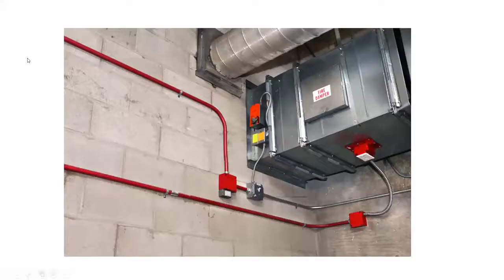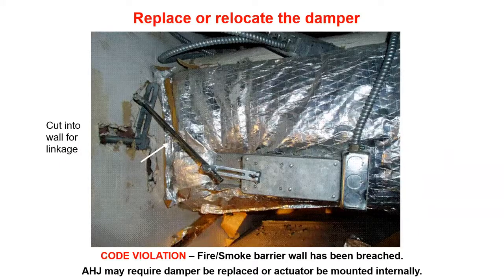Next. Now, when you go to look at some of them, and this one's typical, you can't tell really whether that is a Chapter 9 or a Chapter 7 application. The red conduits give you a definite indication that it was installed by a fire alarm contractor, but we see a mistake up at the top. Oh, fire damper. Well, it's not a fire damper. It's got an actuator on it. It's going to be a smoke damper, or because I can see a high temperature limit, it's a combination fire and smoke damper. So you can't tell just by looking at what anything is. You've got to go up and investigate. And it can be a pain in the neck if the drawings are gone.